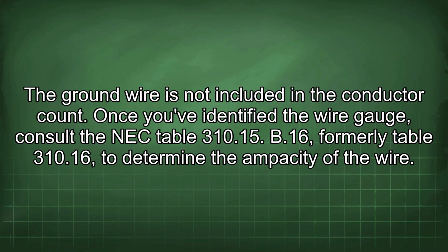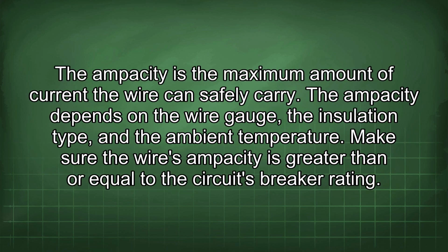Once you've identified the wire gauge, consult the NEC Table 310.15(B)(16), formerly Table 310.16, to determine the ampacity of the wire. The ampacity is the maximum amount of current the wire can safely carry. The ampacity depends on the wire gauge, the insulation type, and the ambient temperature. Make sure the wire's ampacity is greater than or equal to the circuit's breaker rating.